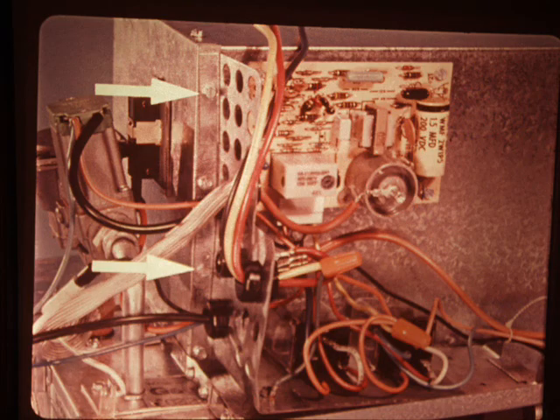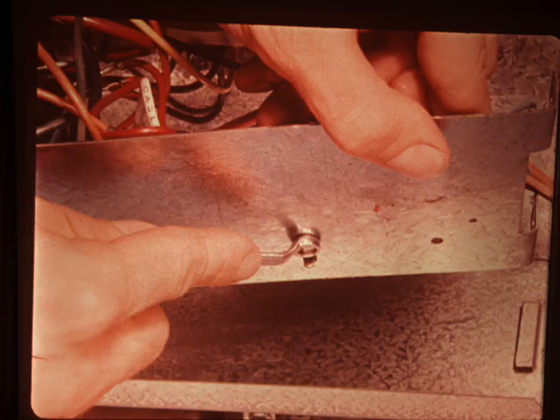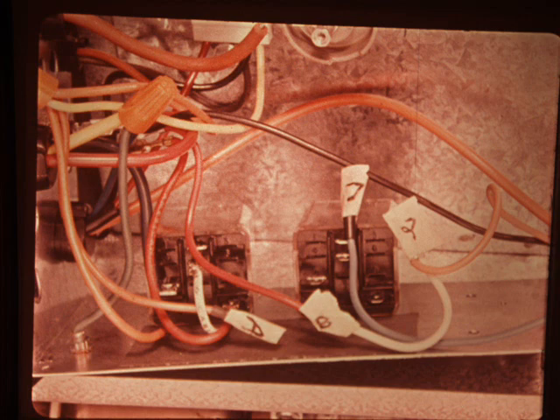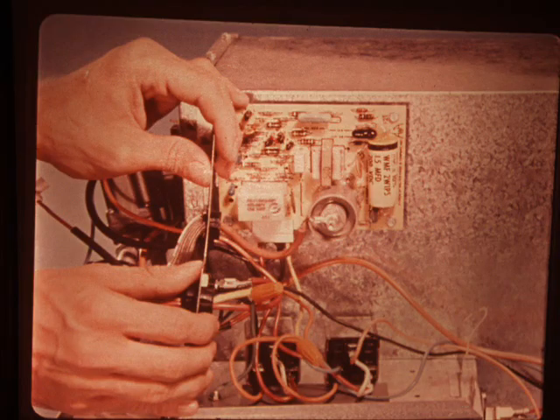To remove either of the blower relays, first remove these 2 mounting panel screws. Carefully raise the panel to give you access to the screws underneath holding the relays in position. Tag the electrical leads when removing either relay. When reinstalling a relay and the panel, be sure the panel engages the mounting tab.